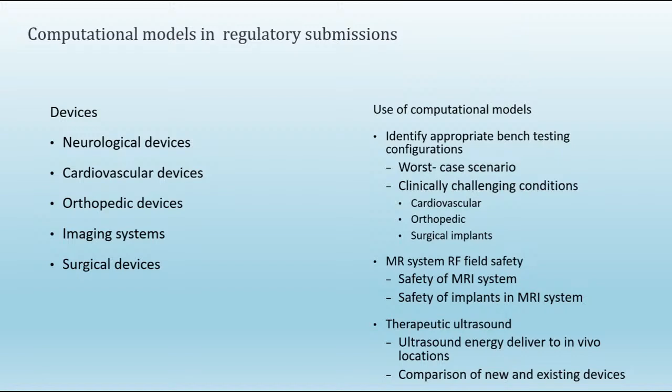We've recently been talking to some folks who are very interested in both of those. We've talked to MRI companies and also companies developing implants, about how they could use simulation efficiently to show that the device they've developed is a derivative of an existing system, so that it reduces the amount of approval that's required. So you model your current system that's already been approved, then you run the simulation on your new device and say, the result shows that it's very similar, and since I have an already approved device, we can go ahead with getting a derivative approval for the new device.